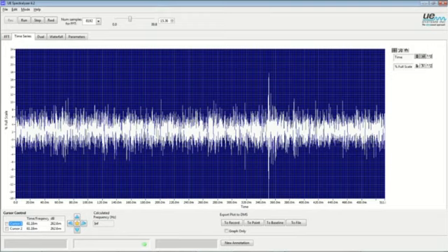The time is self-explanatory. It looks at a specific time in the point of a recording. And within electrical components, there are certain components that should have no ultrasonic emissions. There are other components that have known or normal emissions. And in both cases, when you have other components taking place, you have to be able to pick those out and visualize them. The time analyzer does this the best, in my opinion.